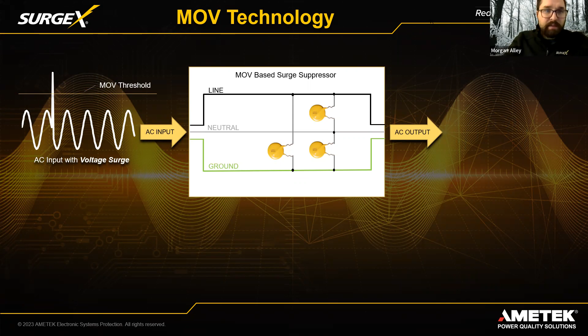Now, what happens when there is a surge in one of these systems and it exceeds the threshold for the MOV? The voltage rises above the clamping voltage, that threshold that the MOV has, and it draws even more current. So what the MOVs do is dissipate current, and you can see with our arrows that we have set up here the path that electricity takes. It'll oftentimes divert directly into ground, and you can see with our red arrow here how it'll actually oftentimes produce an electrical current that will go in the reverse of your circuit. Obviously, that can cause quite a bit of a hiccup with your technology.